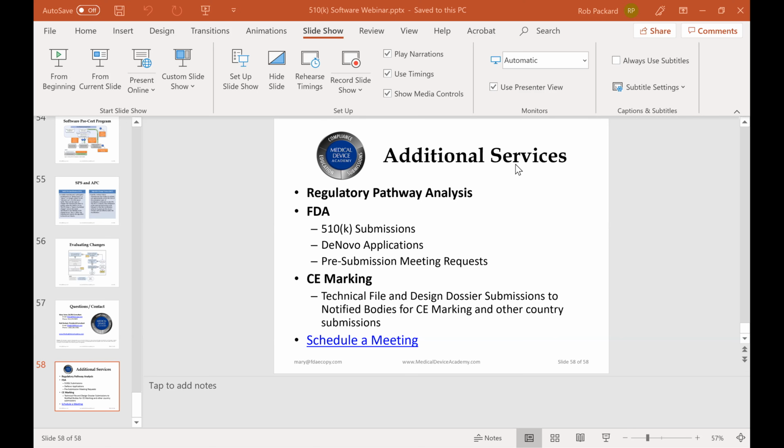But with the special 510K route, if the FDA disagrees that it can be a special 510K and they convert you over to a traditional 510K, you have to, number one, write all the summaries for the special, and then you have to revise your submission and resubmit as a traditional with full test reports. And that's just more work for you. So I would never do a catch-up as a special. You can, but I wouldn't. There's no point in it. If it's a catch-up, then you already are on the market. And by definition, I would just go ahead and give them the traditional because it's less work for you to give them the full report than it is to give them summaries of everything.